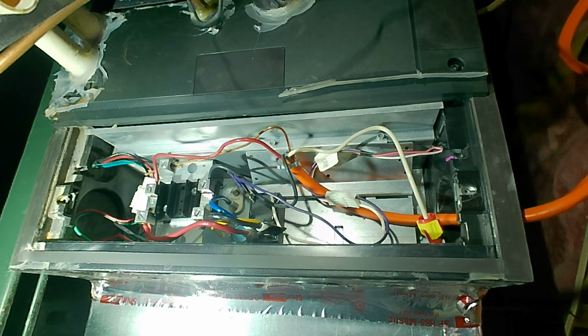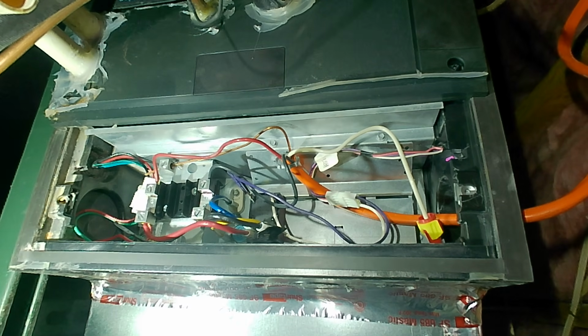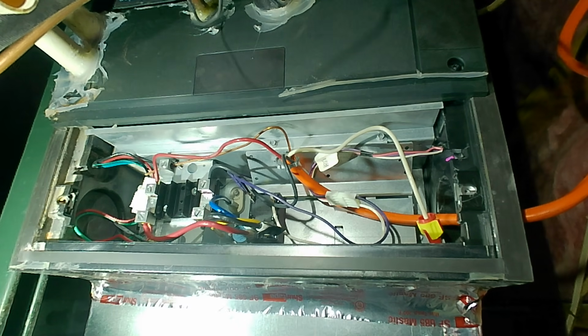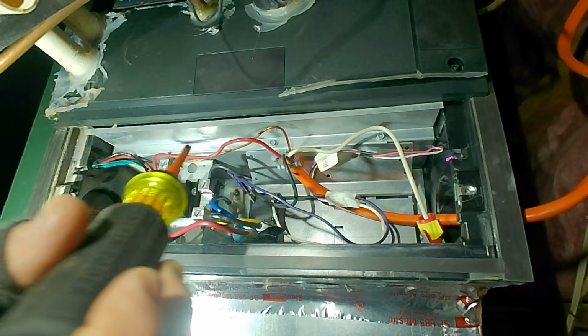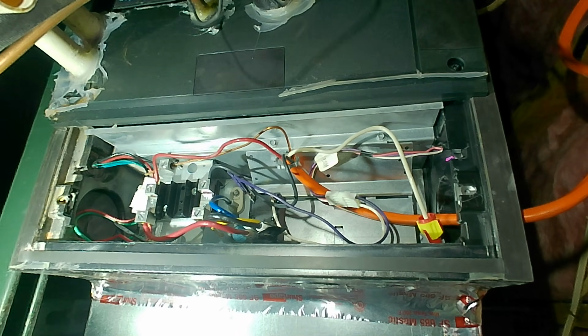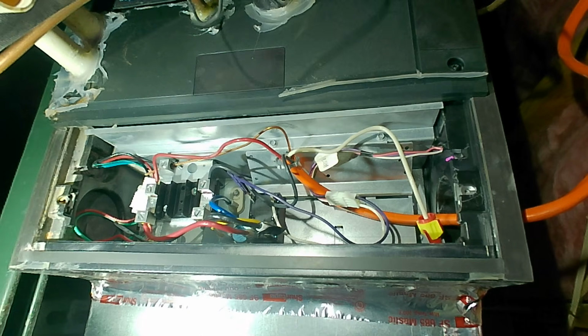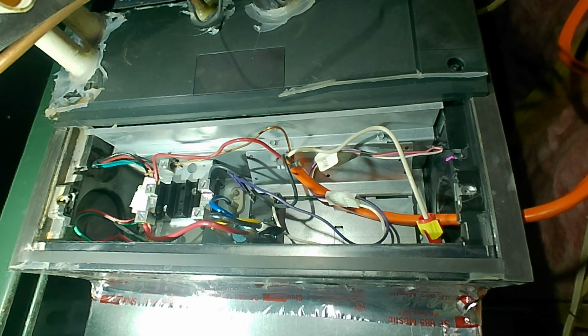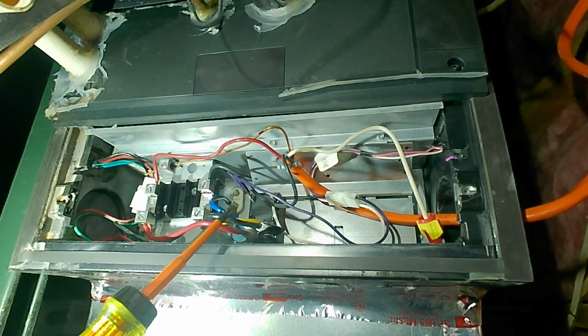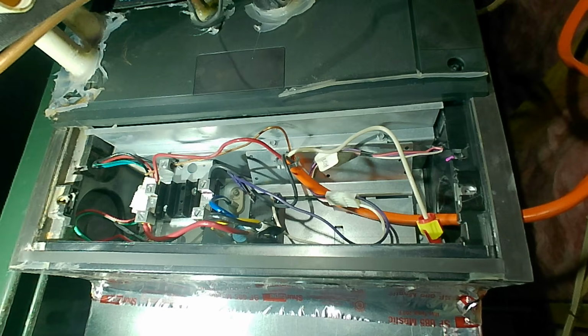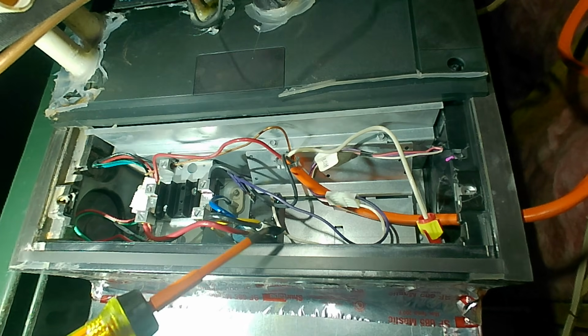So if it's under warranty, we just get the whole set of heat strips and be done with it. But a lot of people would just need a new limit. You got dirty filters, whatever, and then they just put the limit in, turn it on, they come on, then we leave, and then we go back, and then they're out again. Limit's out again.